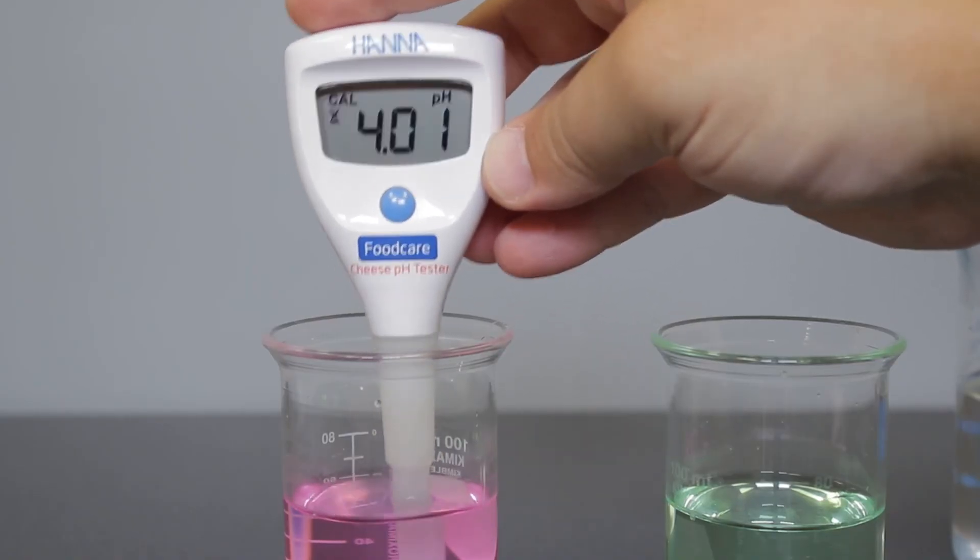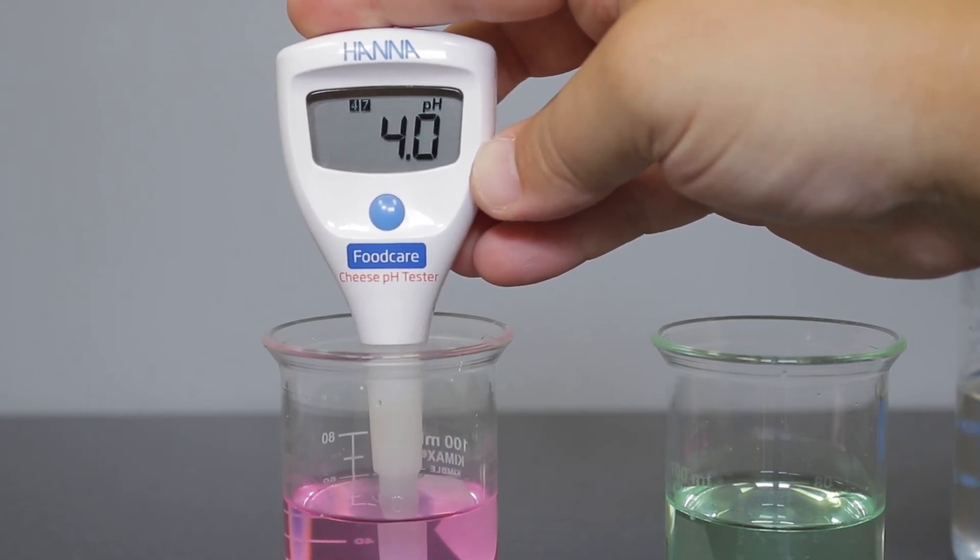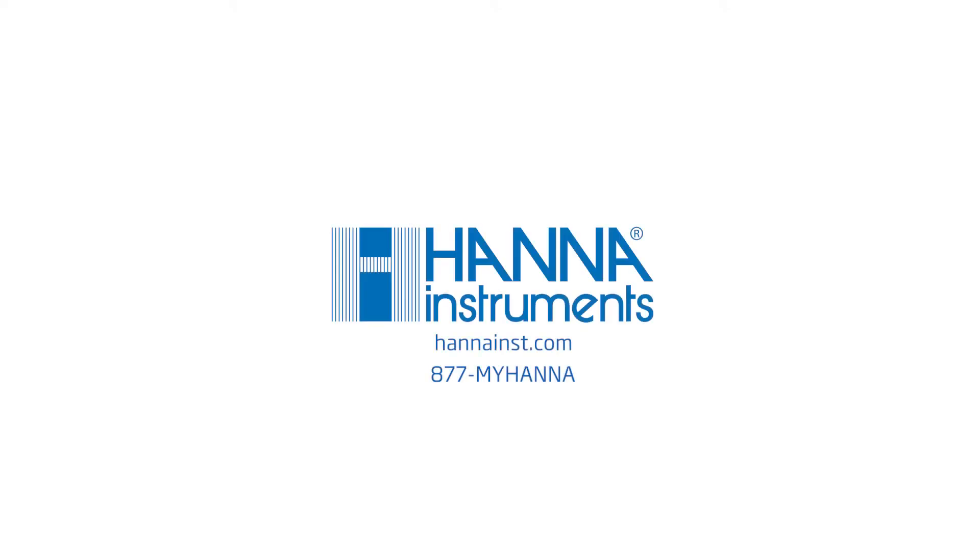Once the second calibration point is stable, "store" will appear on the screen, confirming that the two points are recorded and the tester will return to measurement mode. To learn more about the HI981032 Cheese pH Tester, visit us at hannainst.com.